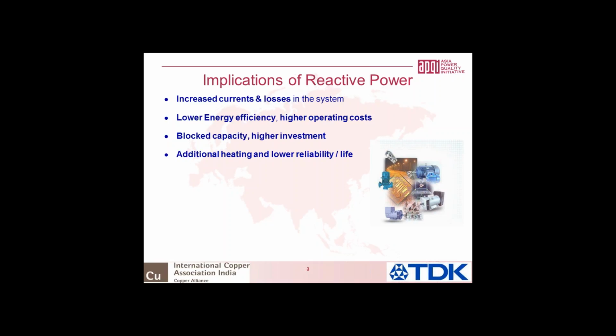Depending on the type of insulation used, it could have an 8-degree rule or a 10-degree rule, which means for every 10-degree increase in operating temperature, the life reduces by almost half.